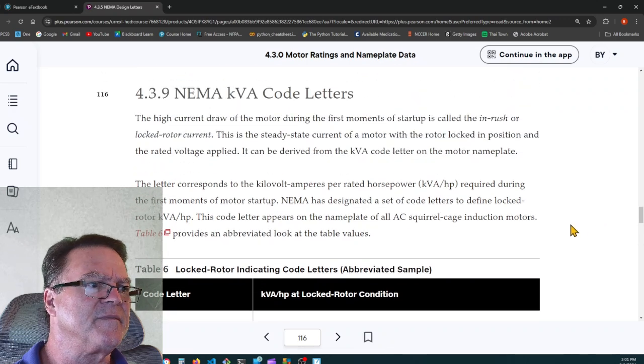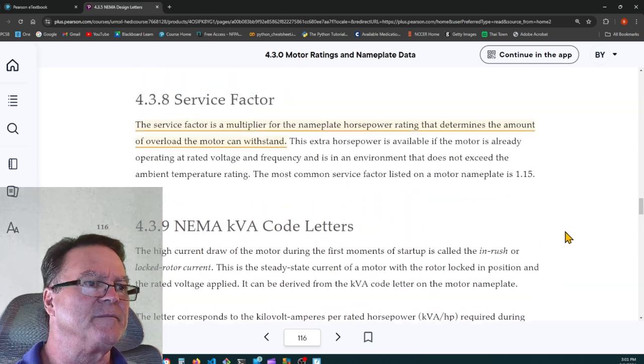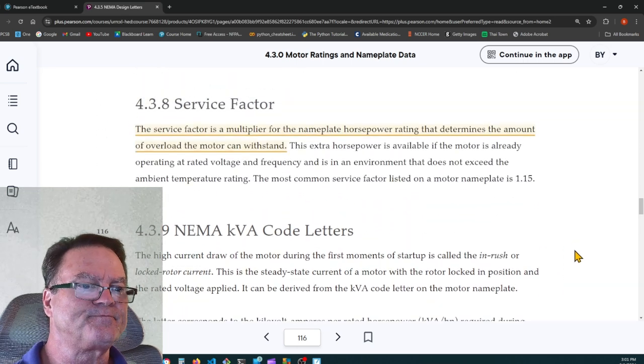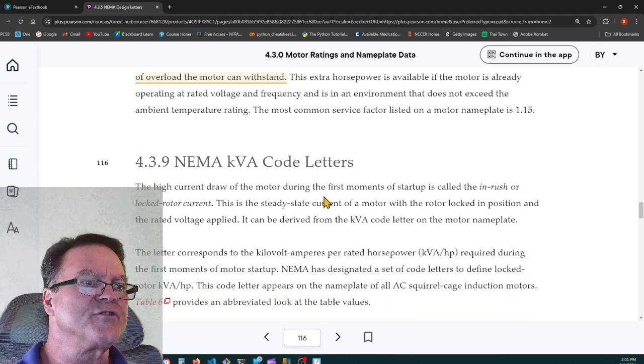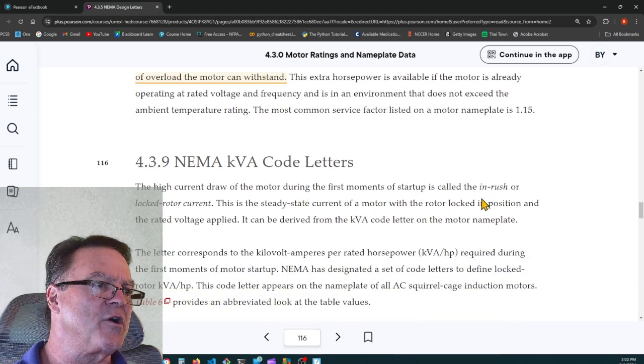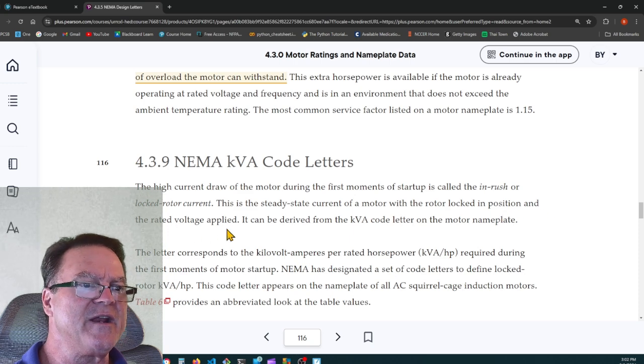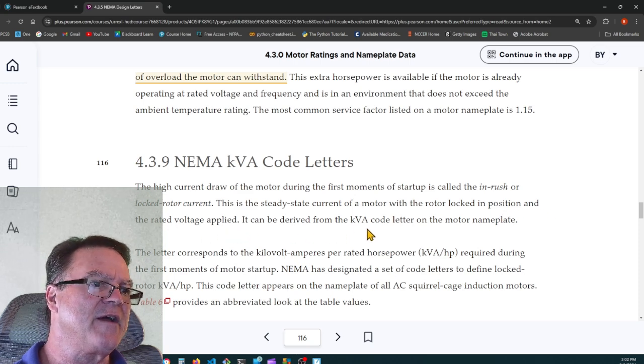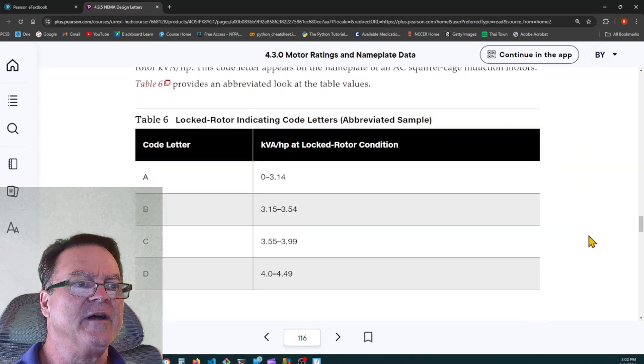Where did they tell us that? They did. All right. The letter corresponding to this is the NEMA KVA code letter. It's the inrush current. The high current draw of the motor during the first moments of startup is called the inrush or locked rotor current. This is the steady state current of a motor with the rotor locked in position and rated voltage applied. It can be derived from the KVA code letter on the motor nameplate.